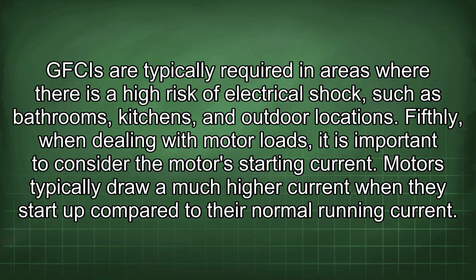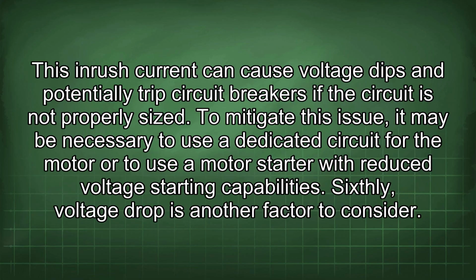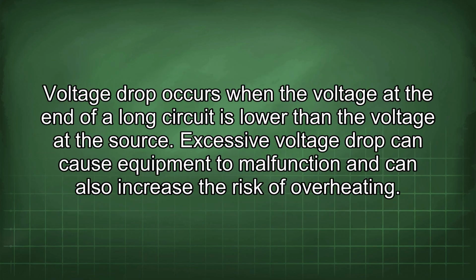Fifthly, when dealing with motor loads, it is important to consider the motor's starting current. Motors typically draw a much higher current when they start up compared to their normal running current. This inrush current can cause voltage dips and potentially trip circuit breakers if the circuit is not properly sized. To mitigate this issue, it may be necessary to use a dedicated circuit for the motor or to use a motor starter with reduced voltage starting capabilities. Sixthly, voltage drop is another factor to consider. Voltage drop occurs when the voltage at the end of a long circuit is lower than the voltage at the source.